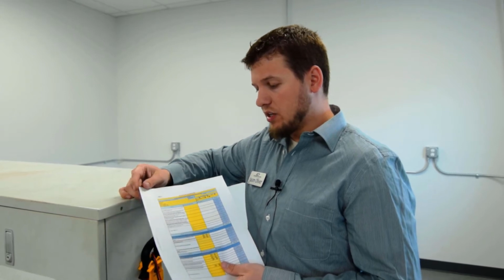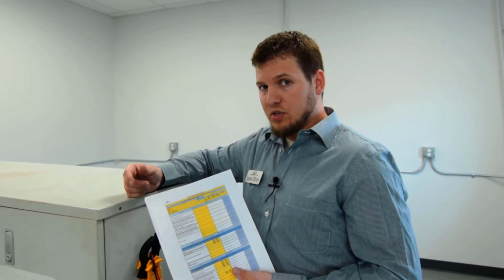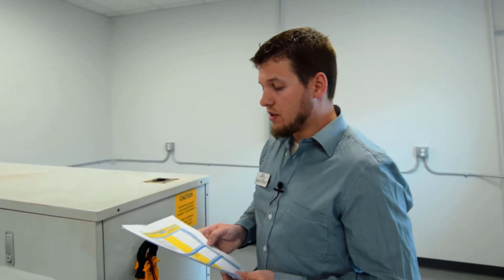Let's go to step number 2 on this checklist. Step number 2 on this checklist is to verify that the condenser coil is clean and there's no damages to it. This is one of the most important parts of the PM cycle.